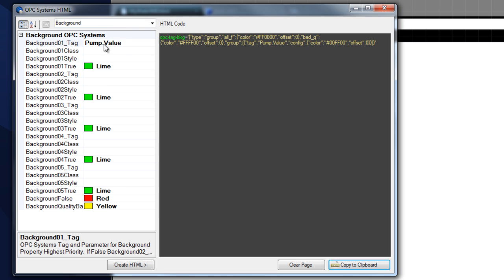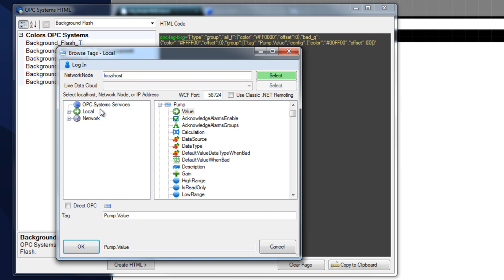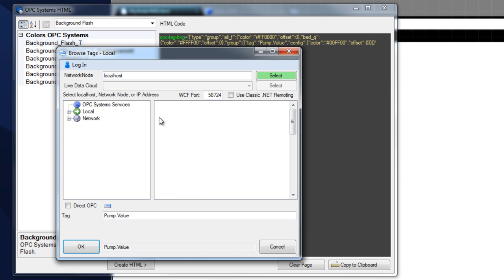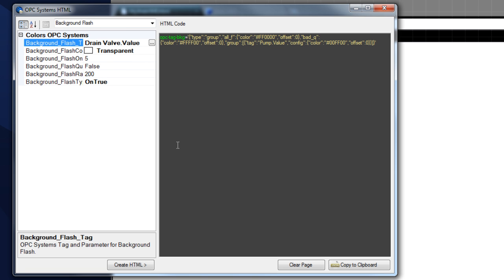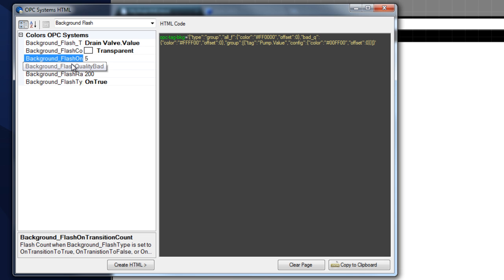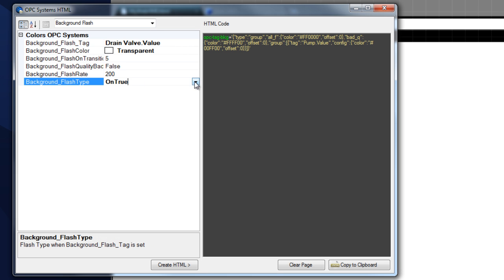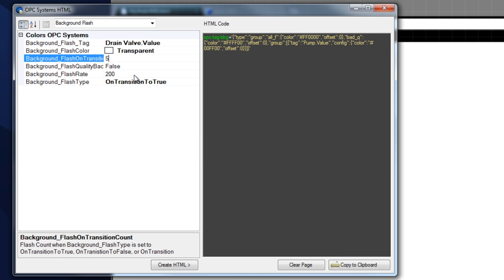Let's go back to our HTML wizard and make our background flash. I'm going to select background flash and select another tag — let's grab our drain valve. This is another boolean point. Select OK. We can define what the background color is going to be. Since we already have a defined color of red, green, or yellow, let's have that flash transparent. We can set a number of times on transition that we'll allow it to flash, or set it to on true or on false for continuous flash. Let's grab on transition to true — now we'll flash for a set number of times.